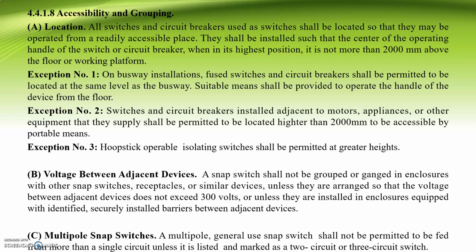A snap switch shall not be grouped or ganged in enclosures with other snap switches, receptacles, or similar devices, unless they are arranged so that the voltage between adjacent devices does not exceed 300 volts, or unless they are installed in enclosures equipped with identified, securely installed barriers between adjacent devices. C, multipole snap switches. A multipole general use snap switch shall not be permitted to be fed from more than a single circuit unless it is listed and marked as a 2-circuit or 3-circuit switch.